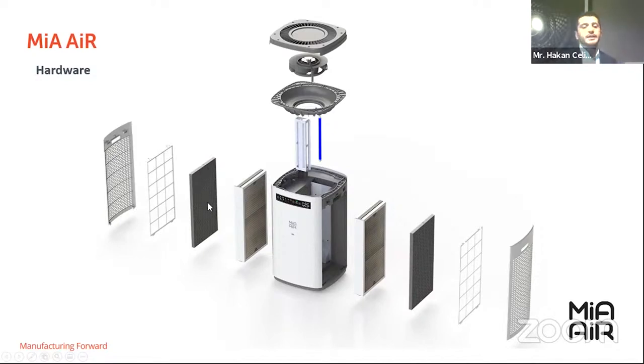We have used the activated carbon filter, granule type, pellet type actually. On each set we have used around 1.9 kilograms of activated carbon in this filter stage. And as I said, we have the H13 class HEPA filters with 8 square meters of area in total. Or we have the H14 class optional HEPA filter, which has 11 square meters of area.